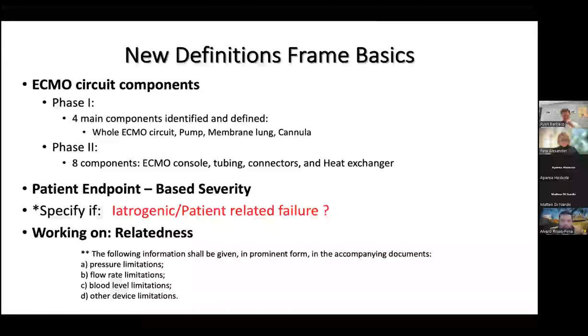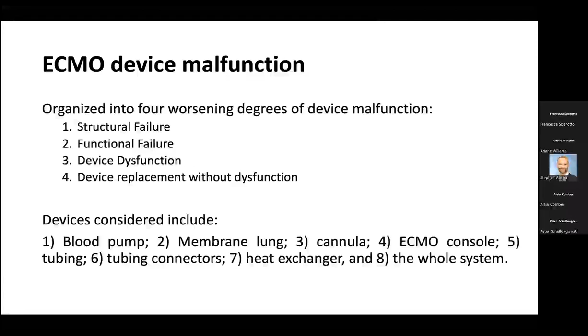The ECMO definition of malfunction was organized into 4 worsening degrees of device malfunction: a structural failure, functional failure, device dysfunction, or device replacement without a dysfunction. We consider the 8 elements of the ECMO system that you see listed here. So the new definitions, this is the summary. Type 1 is a structural failure, defined as anything that impacts the integrity of the device, the separation of blood and air, leading to blood leak, air entrainment or embolus, and is managed with replacement.